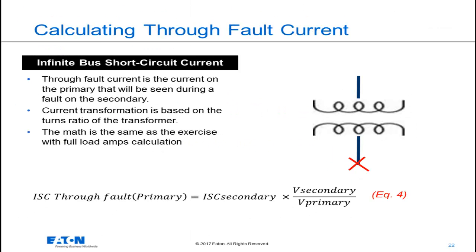When a short circuit occurs on the secondary of a transformer, the current that flows in the primary will not be the same as that being delivered to the fault on the secondary. The difference is going to be dependent upon the turns ratio of the transformer. We can reflect the secondary current to the primary, and this is a simple calculation based upon the turns ratio. The primary current is equal to the secondary current times the secondary voltage over the primary voltage. It's shown here in equation number four.